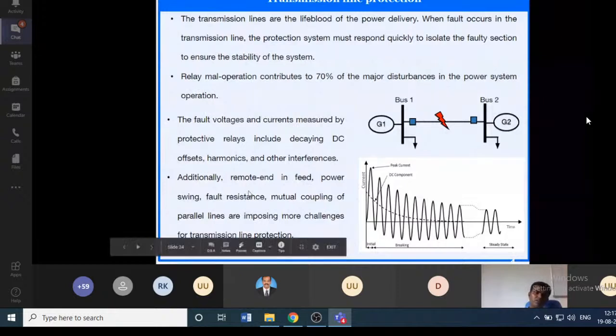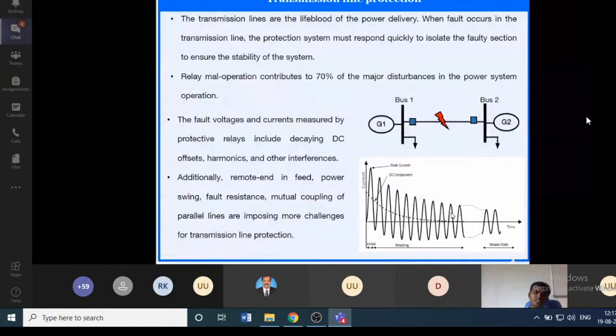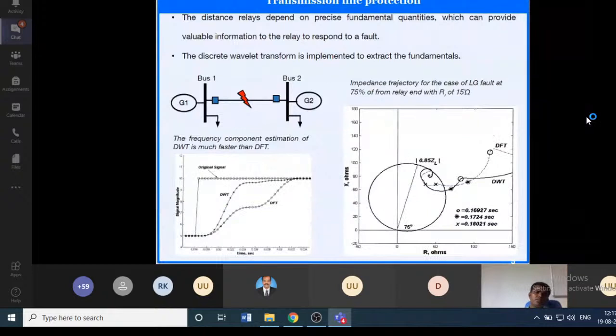In addition to this, we have some more challenges, along with remote end infeed, power swing, fault resistance, and mutual coupling of parallel lines. These are the challenges for transmission line protection. They can be managed with the help of these signal processing techniques. The distance relay depends on precise fundamental quantities; it measures the fundamental components, which provide valuable information for the relay to respond to the fault.